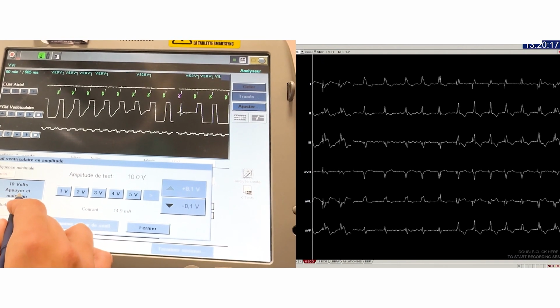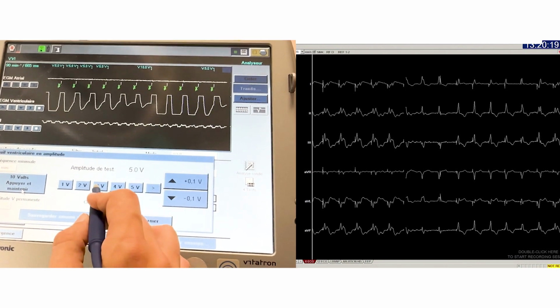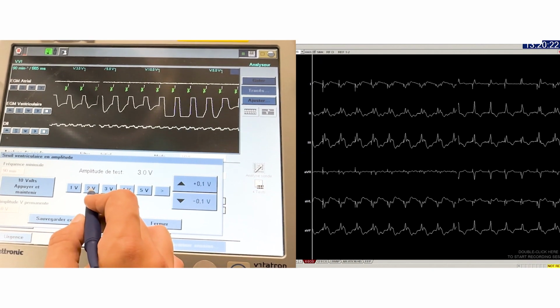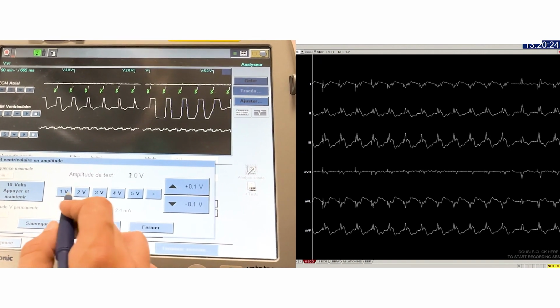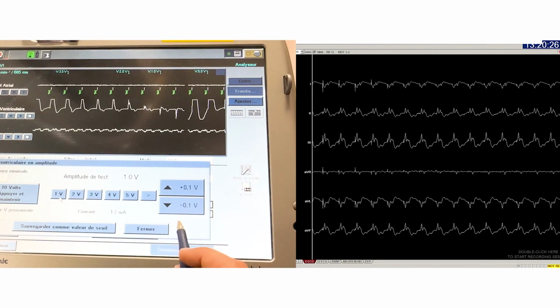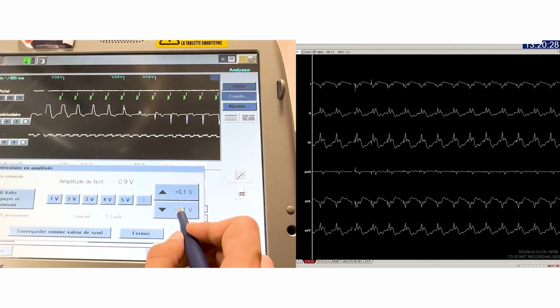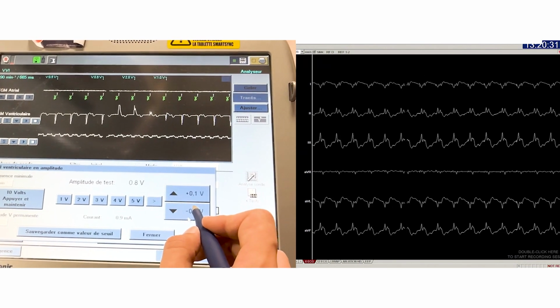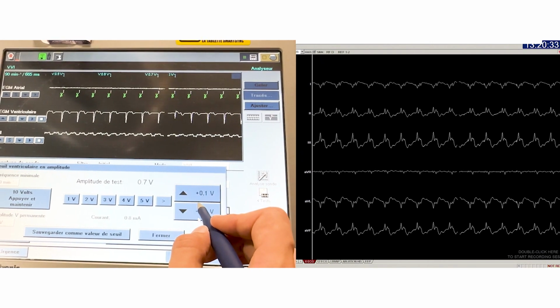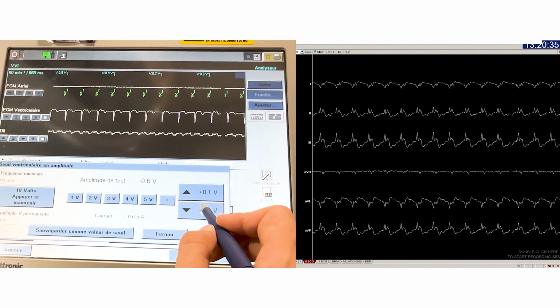Phrenic nerve capture is stable, present at 10 volts but not at 5. The LV pacing capture is still excellent. Well below 1 volt, which is not always the case for this epicardial pacing method without lead fixation.